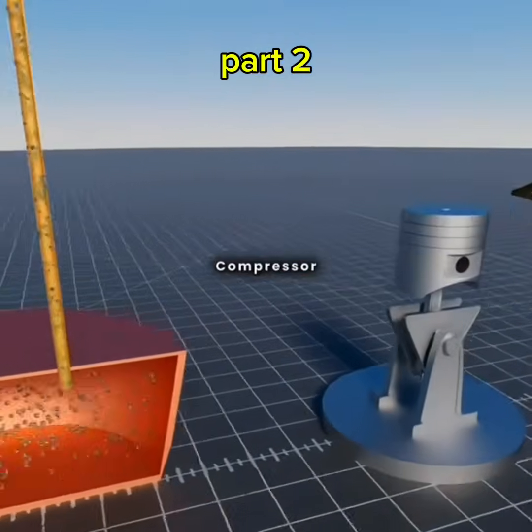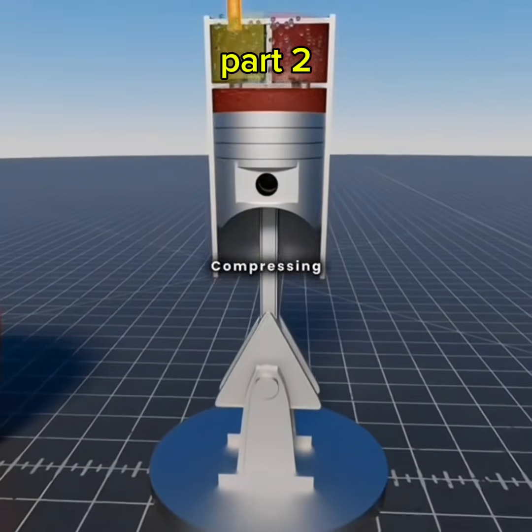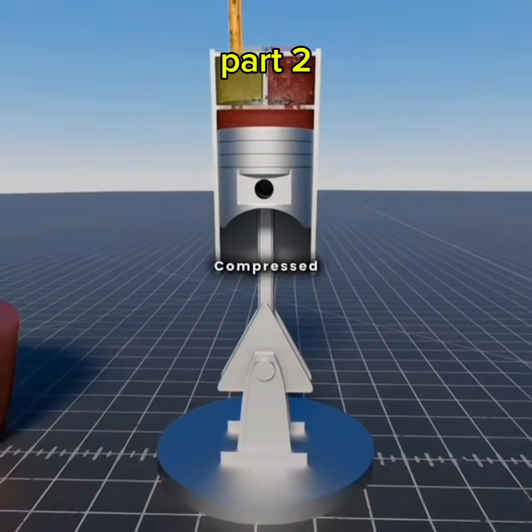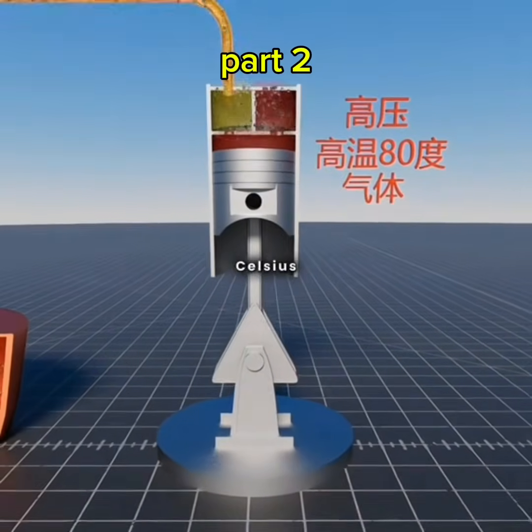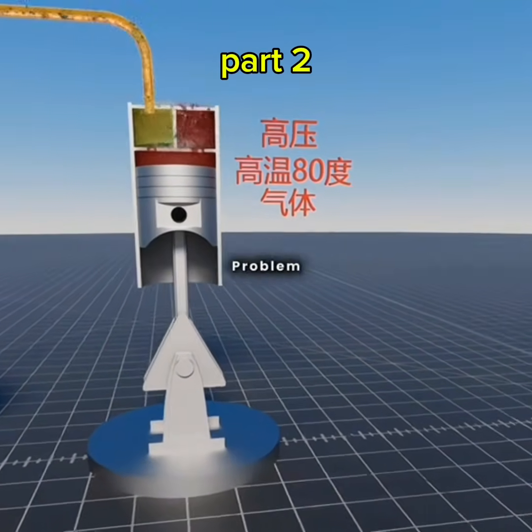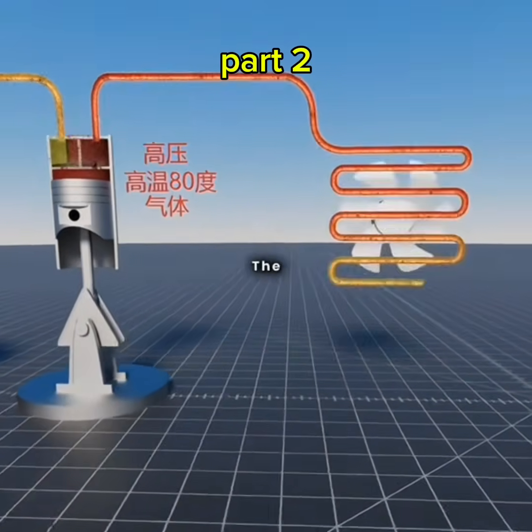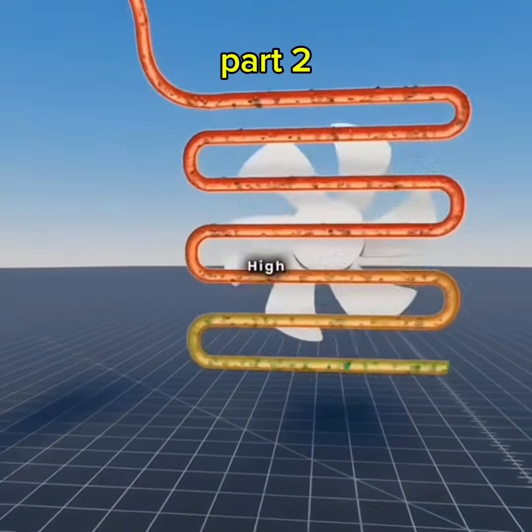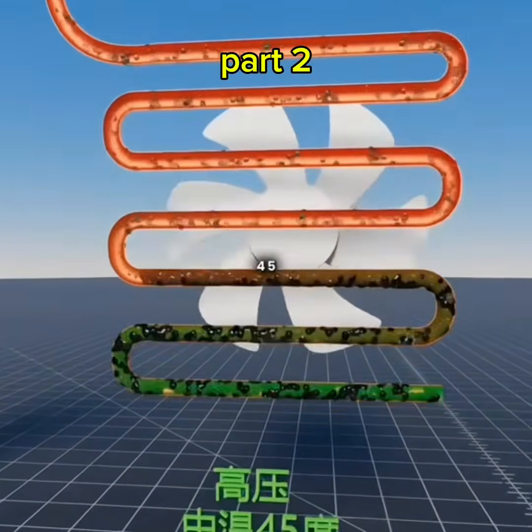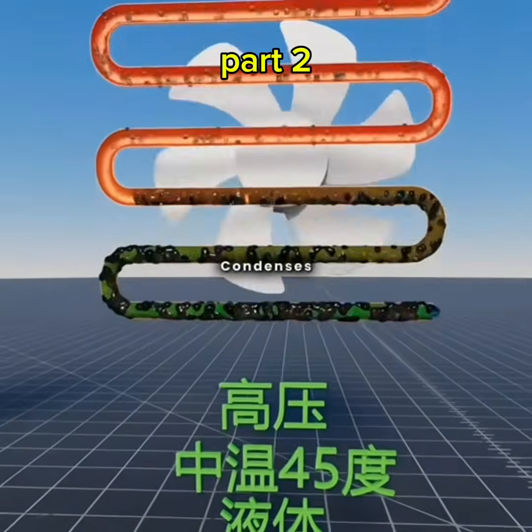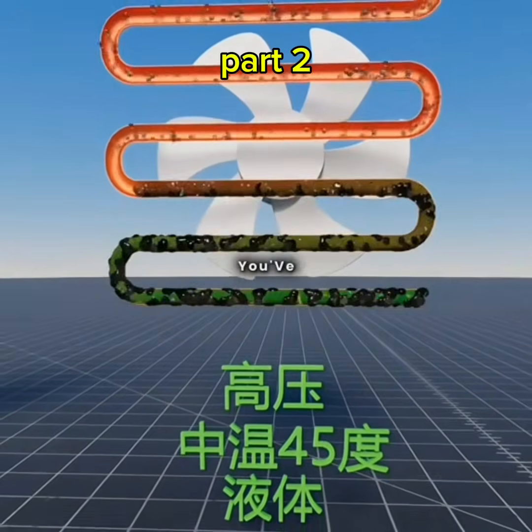So you use a compressor to squeeze the gaseous Freon. But compressing gas creates a lot of heat. The compressed refrigerant may become hotter than 80 degrees Celsius, making it difficult to liquefy. No problem. You add cooling coils and a fan after the compressor to remove the heat. The hot, high-pressure gas cools down to about 45 degrees Celsius and condenses back into liquid. Congratulations, you've invented the condenser.